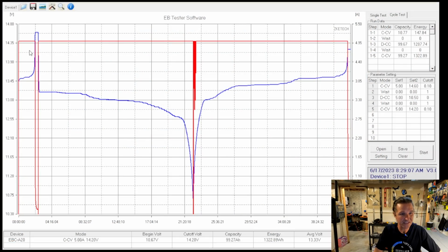What we see here is a graph of when I first plugged it in, and it reached up to 14.6 volts, waited a minute, and then the discharge started. It immediately drops back down to around 13.2, 13.3, and goes all the way down until it reaches 10.5 volts, then waits another minute. Then it goes back up after the charging cycle, and you can see it charge all the way back up to right around 14.2. That's what this curve represents.